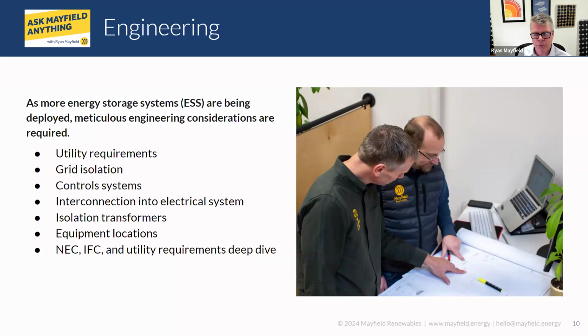Then there's a couple others, and this is probably the more common and more desirable way of doing it - automatic. So making sure your energy storage system can indeed meet whatever loads are automatically connected - that's a requirement in code. Or you can use energy management systems, which are becoming more available and popular, that you can integrate as well, so the energy management system makes sure the loads connected don't overload the battery system or the backup system. So those are some of the methods we're using.